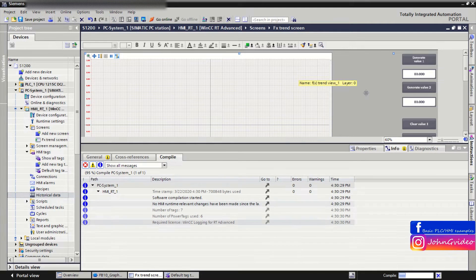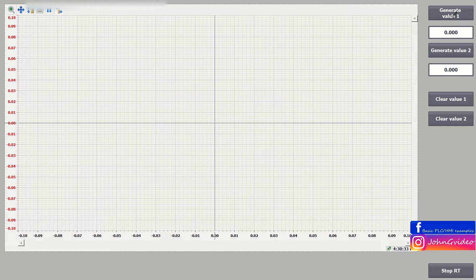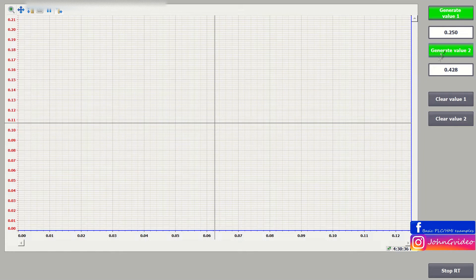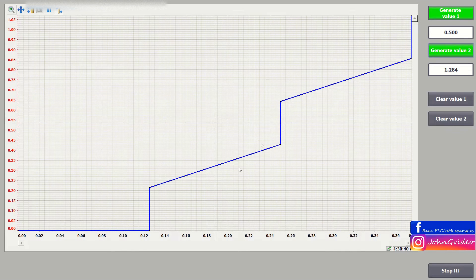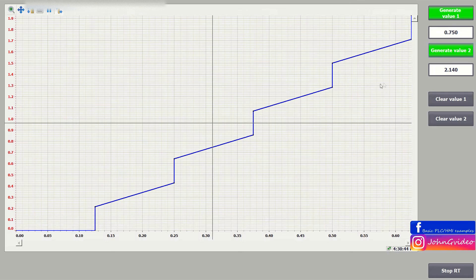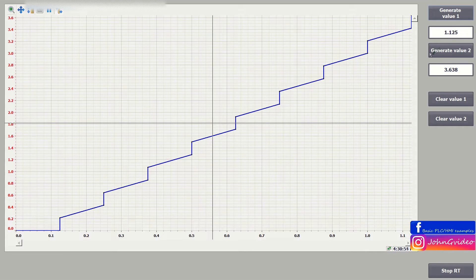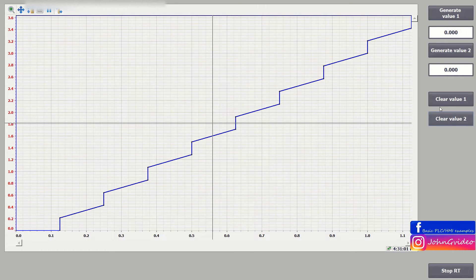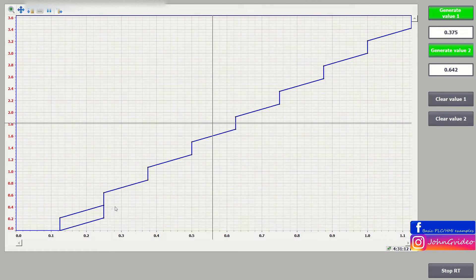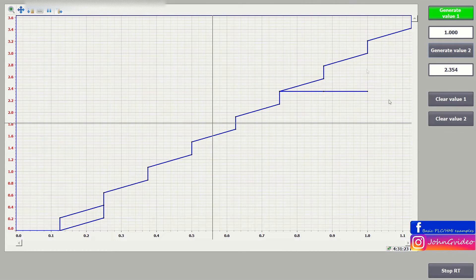We can start the application. Here you can see we generate some data in the PLC and these data are displayed on the FxTrend view. The problem is when we stop generating this data and clear this data in the PLC, the data are still logging into our data log. And when we again generate the values, you can see on the trend view the FxTrend view is still displaying previous data as well as actual data.